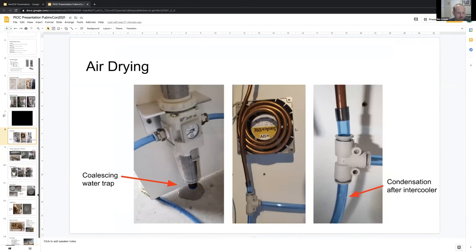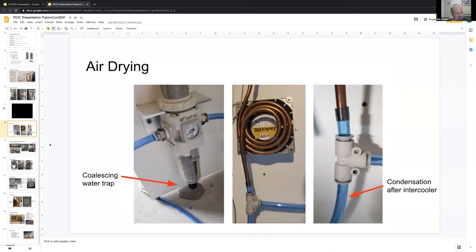So quickly, from that first prototype, I've been looking at different problems that have been found. I'll go through these briefly. One of them is the air treatment. The end goal is to produce medical grade oxygen, which has some very high requirements. So we need to produce very dry air. We need to get all the water out, the oil out, and it could be air pollution as well. That's just the first stage before we then separate the oxygen and the nitrogen.